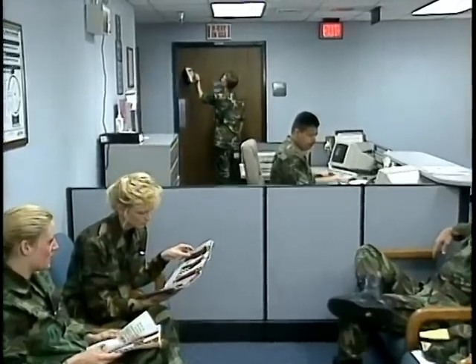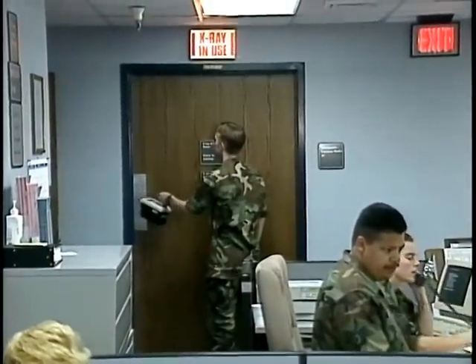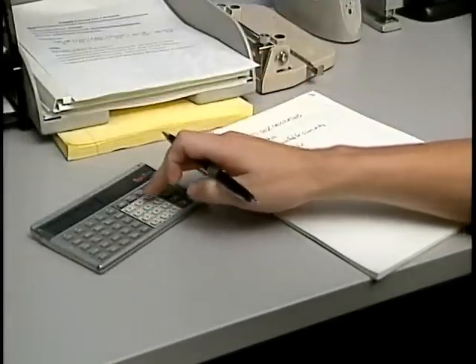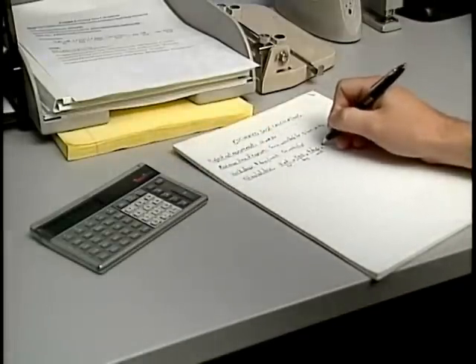Measurements are taken where all potential exposures may occur, including any possible public areas. The RSO or qualified technician then uses the measured radiation rates and reported usage rates to determine the maximum worst-case exposure a worker or a member of the public could be exposed to.